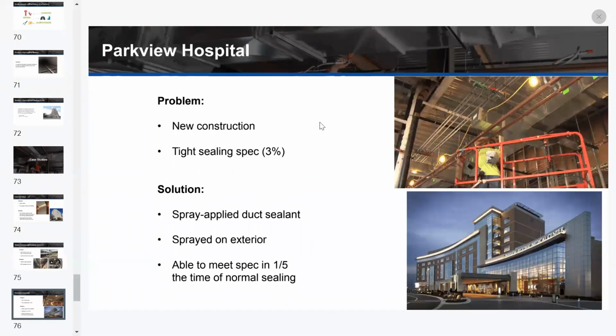Anyways, Parkview Hospital, new construction job with around 32 miles of linear feet of duct, which equated to basically over 100 miles of joints and seams to seal. Since it was a hospital, they wanted to use a product with minimal VOCs that would allow them to meet the tight sealing requirement of 3% leakage. Contractor used a water-based spray-applied duct sealant with minimal VOCs. Our spray seal product allowed them to drive the sealant to the joints and seams, because you're using it at high pressure. They were able to meet the sealing spec and be under 3%. And they completed the job in about a fifth of the time that it would have taken them to do a traditional bucket and brush.